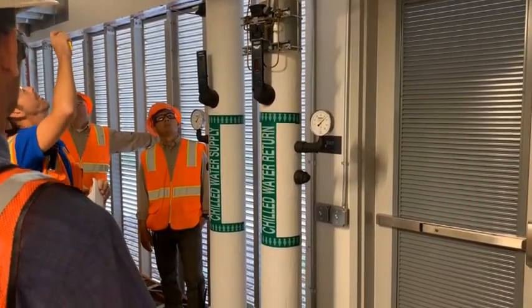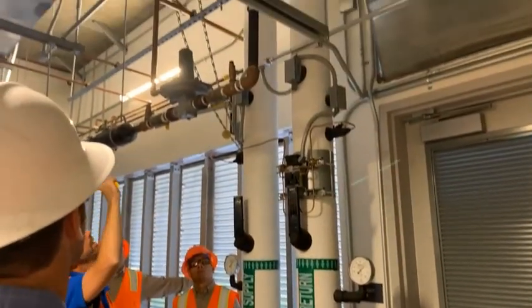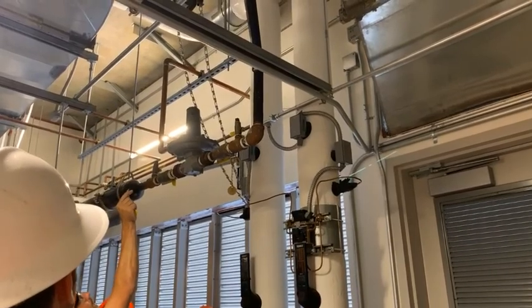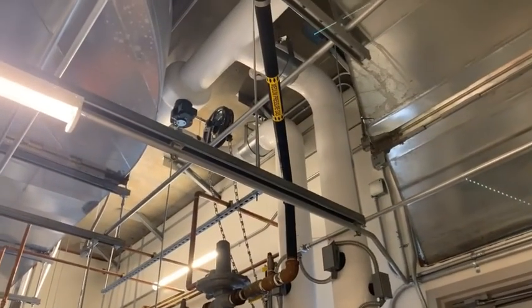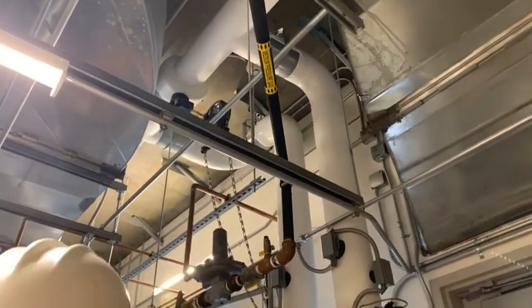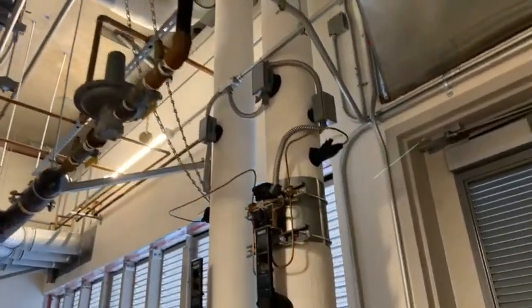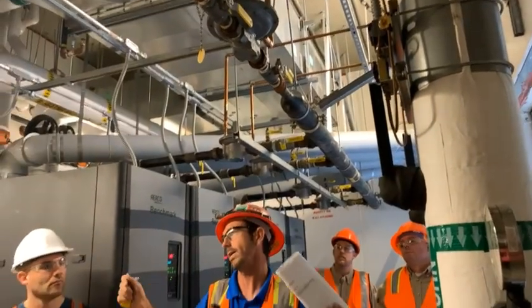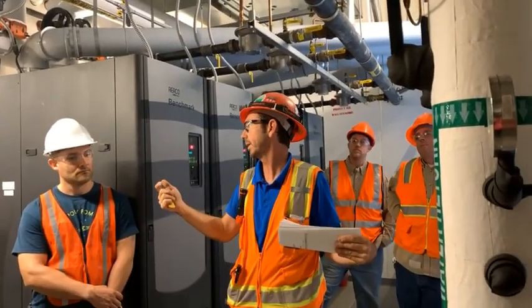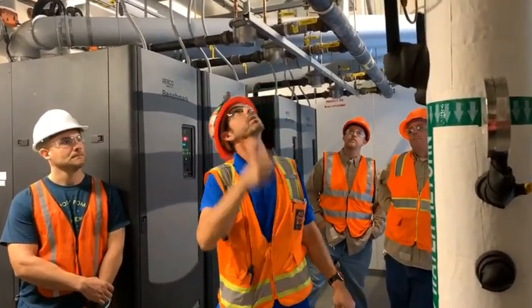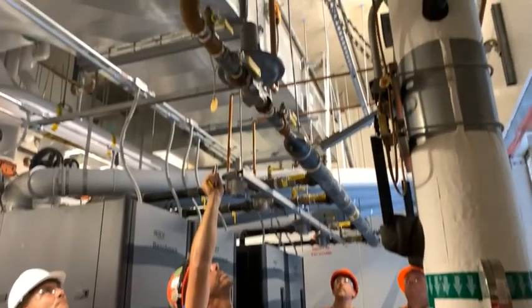Coming up, for our flushing procedure, we have a bypass loop right here. This valve is going to be a normally closed valve. It's this chain wheel operator right here. Normally closed. If it's open, you're going to kind of create like a primary secondary loop with your central plant and the building. Okay? Normally closed valve right here.